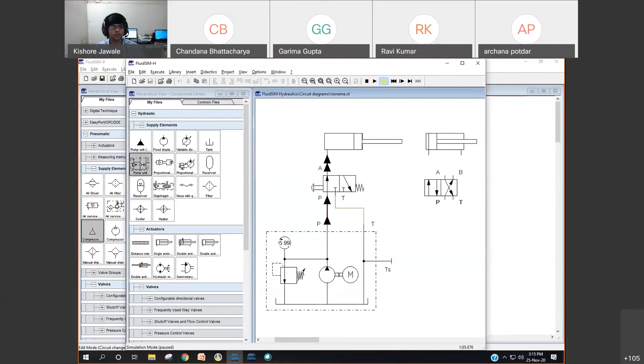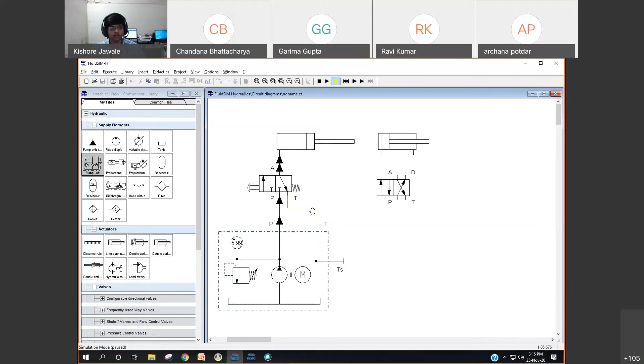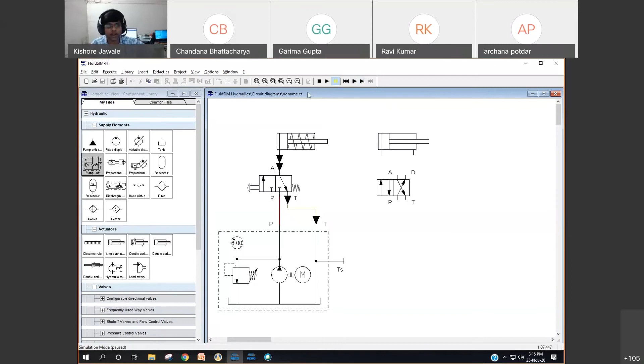Okay, in the next instance, I'll release this push button. When I release the push button, what will happen? Because of the spring, the direction control valve will return back to its initial state. And now whatever fluid is available in this particular compartment can flow via port A to port T. So this spring, which is on the piston rod side, will push the piston ahead, and that liquid will flow from port A to port T and will return back to the tank. You can see. So this is how the actuator works.